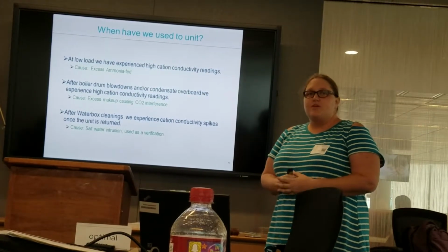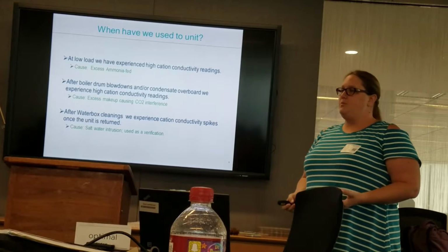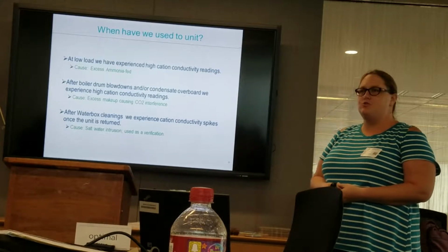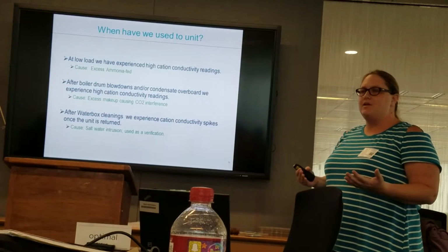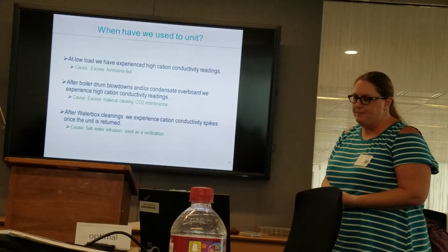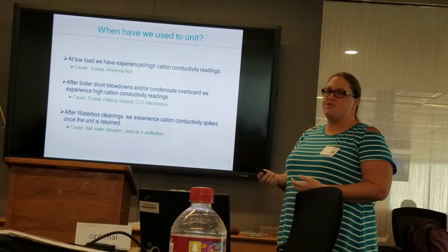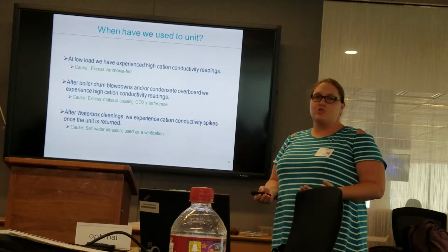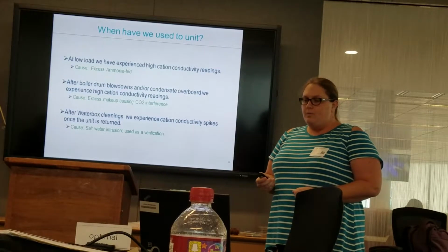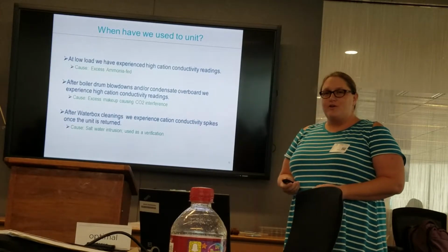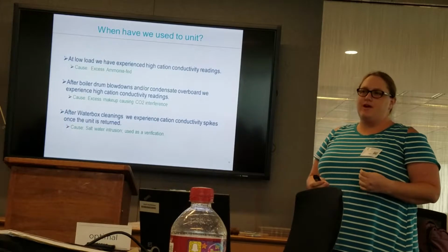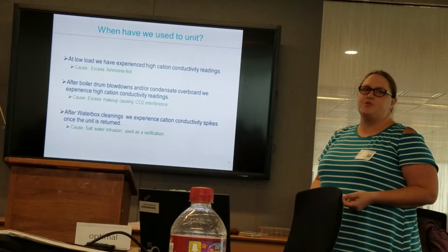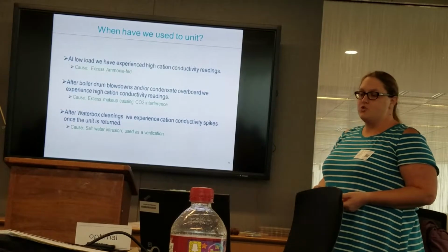Overall, the station is very pleased with this instrument. It has helped them many times with their chemistry excursions to figure out what exactly the data was telling them. We do plan on purchasing the other, more inline degas cation conductivity in the future now that we have funding. But we will definitely use the Mark 24 for the other sample lines that don't have the analyzers. And I actually have other stations that have used this analyzer to verify their inline analyzers are reading correctly.